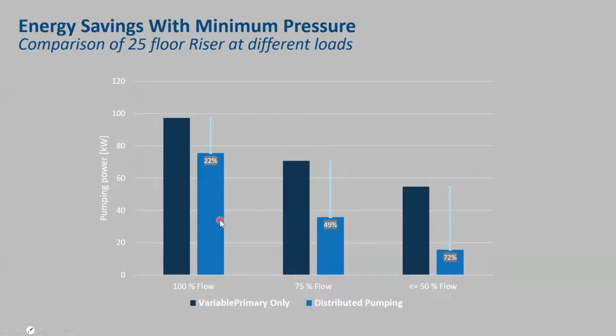And then the lighter blue represents the savings associated with replacing those control valves with distributed pumps. At 100% flow, we're starting to see a little bit better than 20% savings. As we go to 75% flow, which is where we're starting to spend more of our operating hours, we start to see a bigger return.